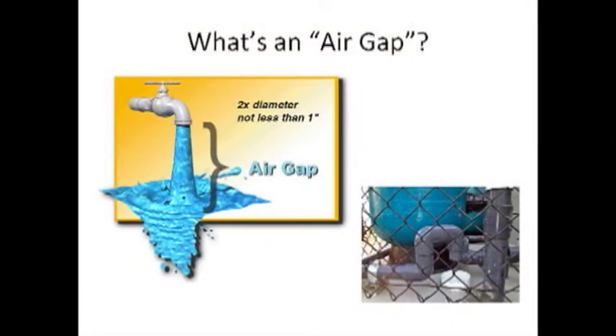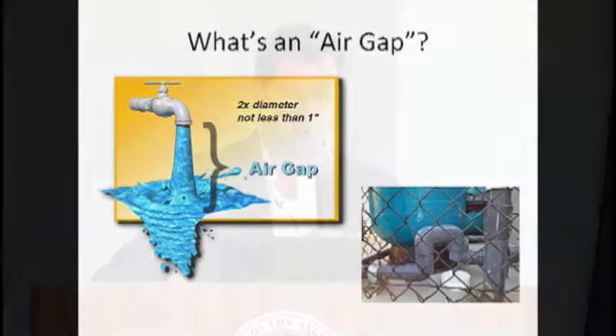With graywater, since graywater is technically wastewater, an RP device and a cross-connection is not allowed under the various codes. The only way for makeup water in that situation is with an air gap, and that's something you will undoubtedly come across when implementing projects.